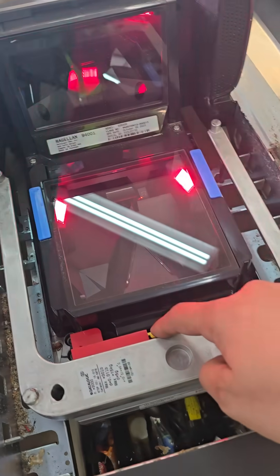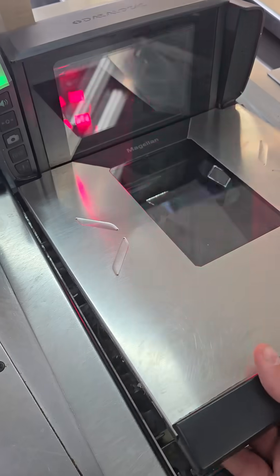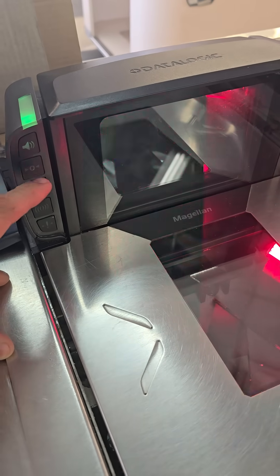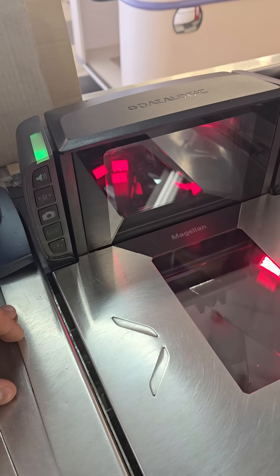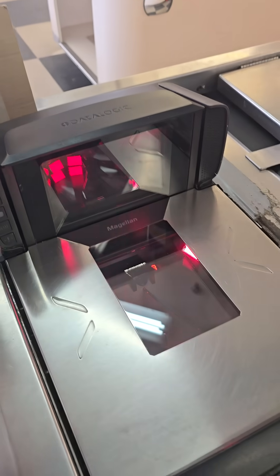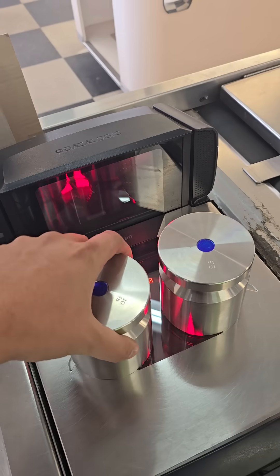Press the yellow button — you'll hear a series of rapid beeps that indicates the calibration procedure has started. There's a zero button over here. When I press this after putting the cover on, I'll hear two beeps, which means it did a zero calibration and that the calibration test point is in pounds.